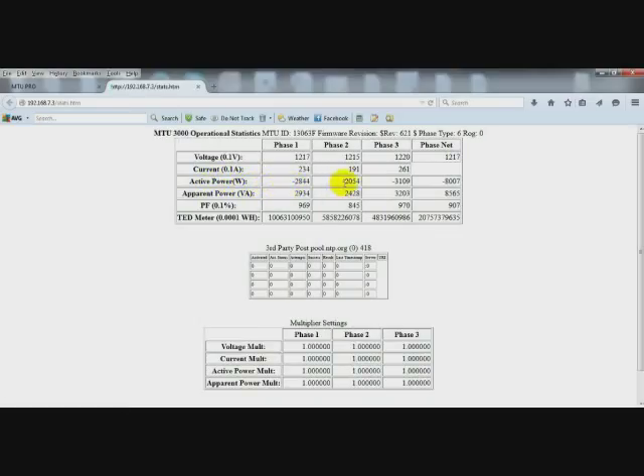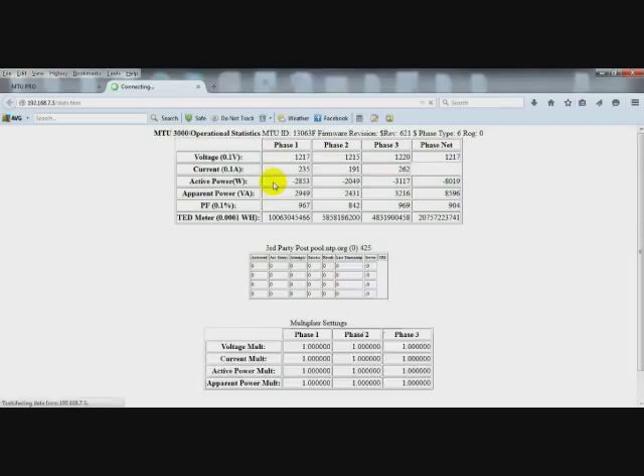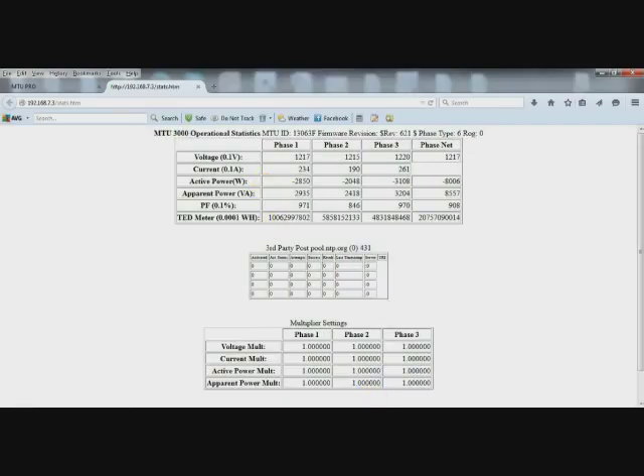So we see on all three phases that we need to check our CT connections. First thing we do is make sure that the polarity is correct, the red dot facing toward the utility. I've already done that. So we know that the CT connections are not matching the voltage as far as A, B, and C phase.